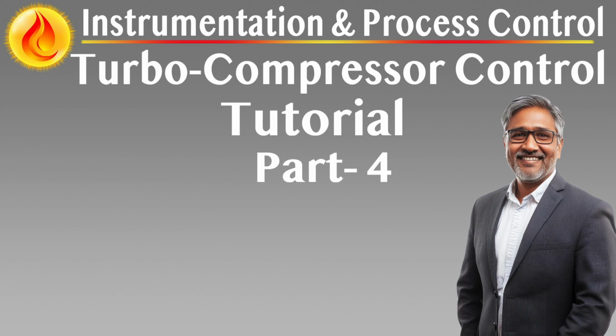In the event of HMI failure, compressor operation continues uninterrupted. All critical data remains available at the DCS via OPC communication. Maintenance personnel can restore functionality using spare licensed software and backup configuration files. The HMI thus acts as a powerful tool for monitoring, managing, and maintaining the turbo compressor system without introducing risk to real-time control or safety.